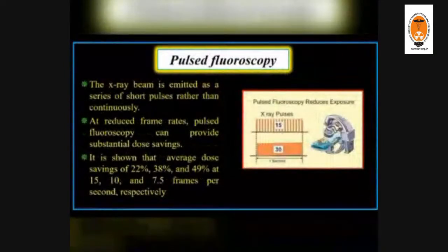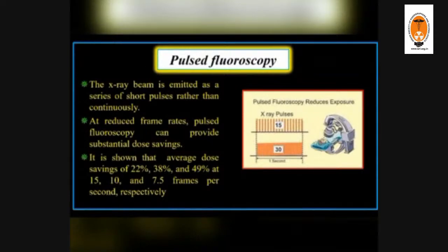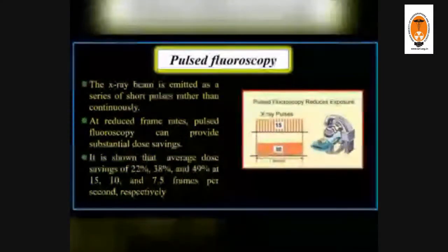Pulsed fluoroscopy. The X-ray beam is emitted as a series of short pulses rather than continuously. At reduced frame rates, pulsed fluoroscopy can provide substantial dose saving. It is shown that average dose saving is 22%, 38%, and 49% at 15, 10 and 7.5 frames per second respectively.